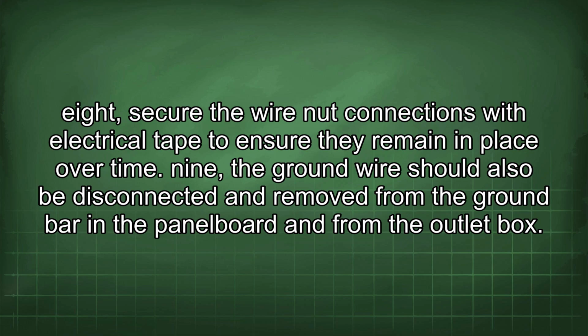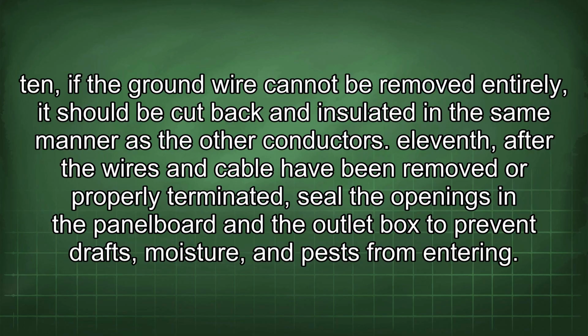9. The ground wire should also be disconnected and removed from the ground bar in the panel board and from the outlet box. 10. If the ground wire cannot be removed entirely, it should be cut back and insulated in the same manner as the other conductors. 11. After the wires and cable have been removed or properly terminated, seal the openings in the panel board and the outlet box to prevent drafts, moisture, and pests from entering.